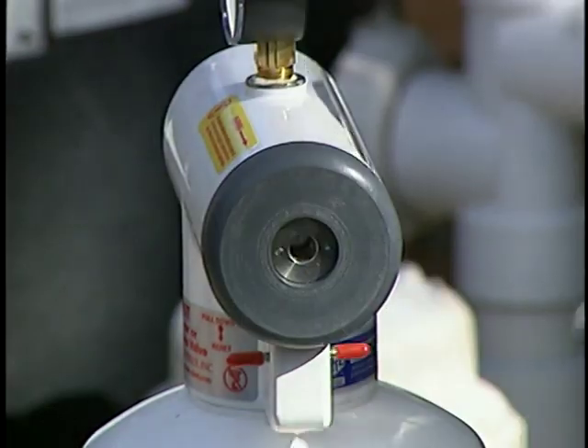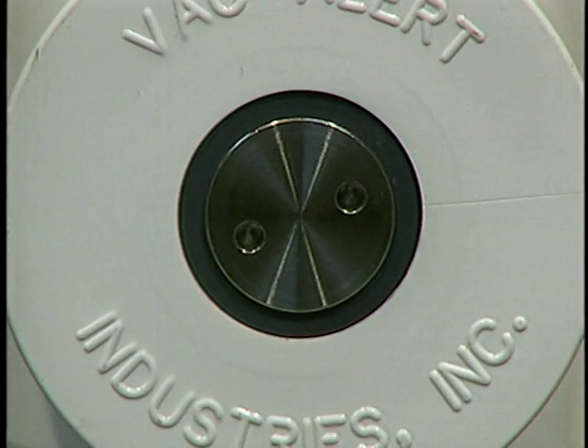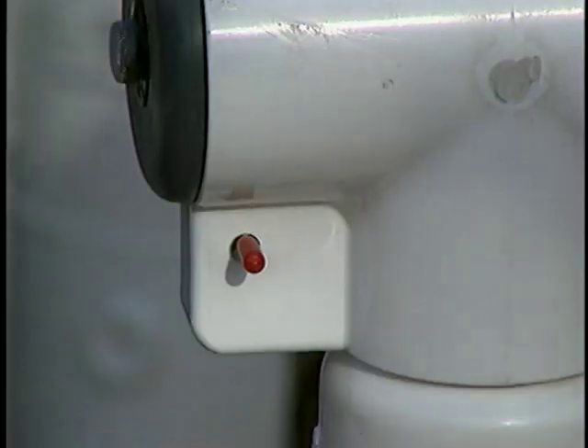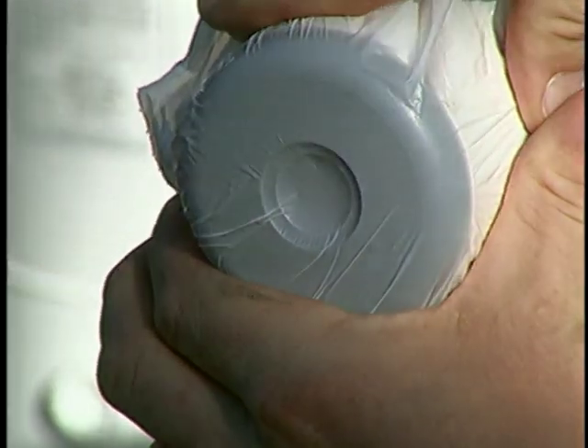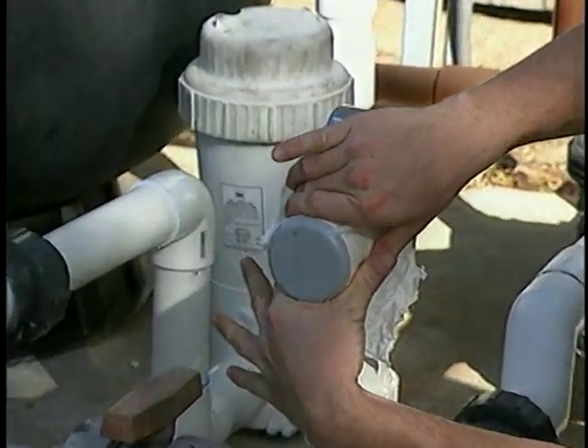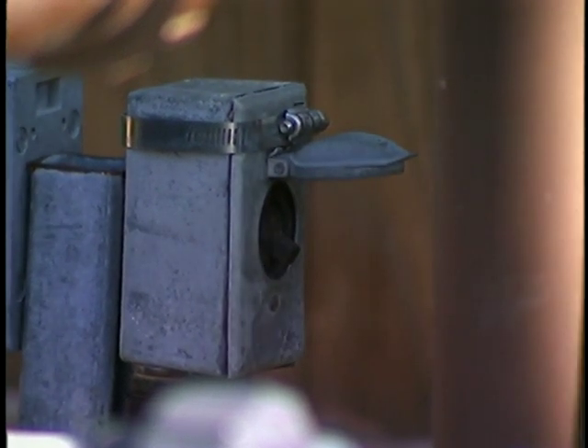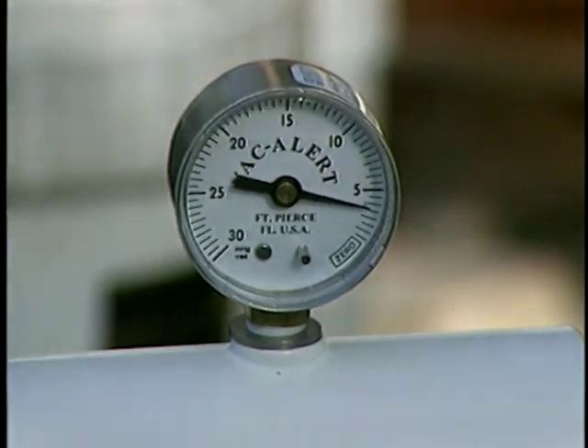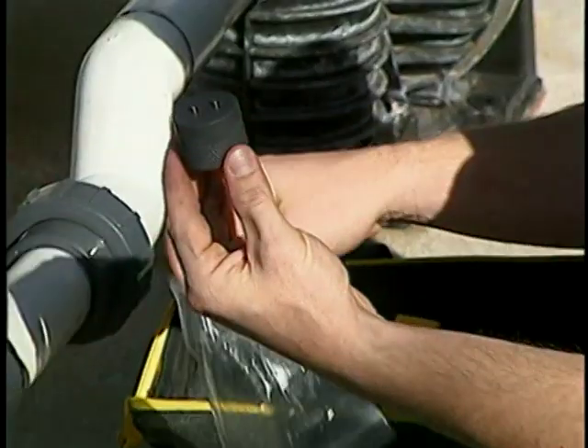To eliminate an air leak, you must turn off the pump. Using a screwdriver, push in the piston until you hear it lock in place. Remove the security cap with the special tool supplied with your unit. Turn the adjustment screw clockwise three full turns to increase the spring tension. Release the lockout mechanism, restart the pump, and recheck for the air leak. If air continues to leak, repeat these steps in increments of three full clockwise turns of the adjustment screw until there is no more leak. Be careful not to over-calibrate the unit, as this may delay valve reaction time. Once the unit has been calibrated for running vacuum levels, turn off the pump for one minute and restart the pump to make sure the SVRS is calibrated for pump startup. Make any final adjustments to the adjustment screw to ensure the SVRS does not react to pump startup. After final SVRS calibration, replace the security cap and the vent screen. Store the special tool for future use.